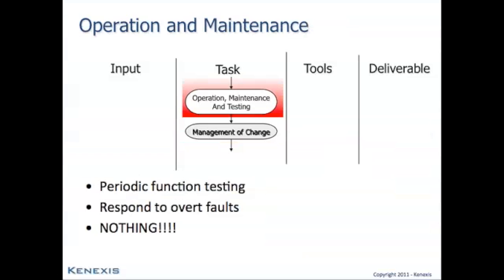After pre-startup acceptance testing, you're off to the normal operation and maintenance phase. During the operation and maintenance phase, you will need to perform periodic function testing and maintenance to maintain the FGS at its safety availability target and at its performance detector coverage target. You'll also need to respond to overt faults in the system with corrective maintenance tasks. And other than that, hopefully, nothing will happen. The best situation is to invest in a good, well-designed fire and gas system and have it never activate. But you will know that if it's necessary, if fires occur, if gas releases occur, that system will be available to take the mitigative actions that it's been designed to perform.